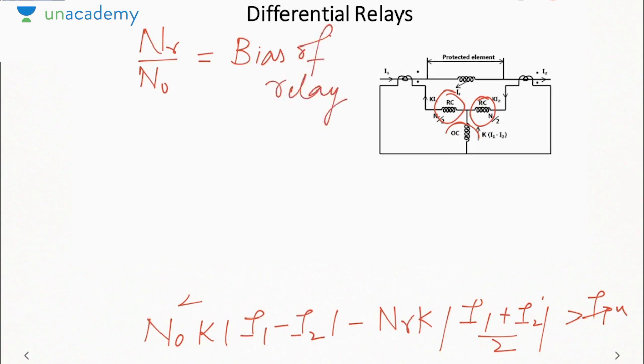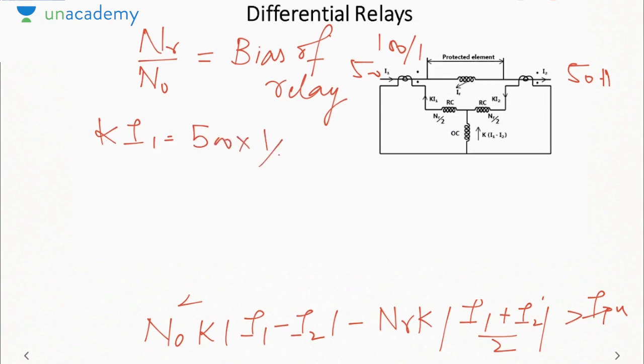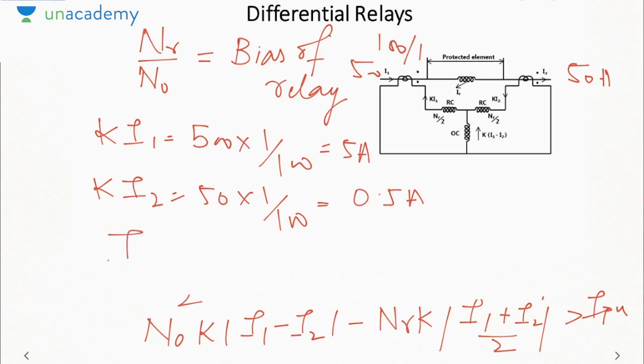Okay. So let us take an example here. Suppose the turns ratio is 100:1. Here we have 500 ampere current. Here I have only 50 ampere. Then this current will become here KI1 will be 500 into 1 by 100. So 5 ampere. KI2 will be 50 into 1 by 100. That is how much? It will be 50 by 100, that is 0.5 ampere. So operating current will be 4.5 ampere.